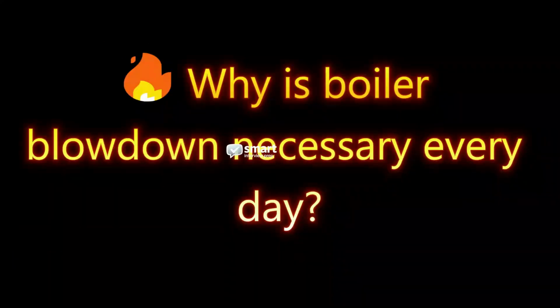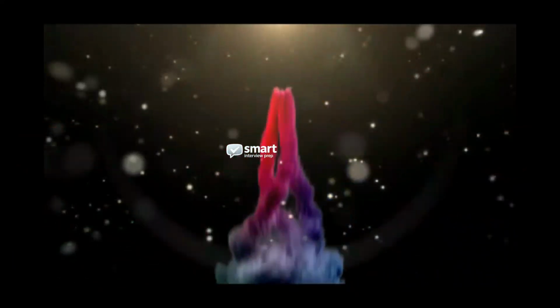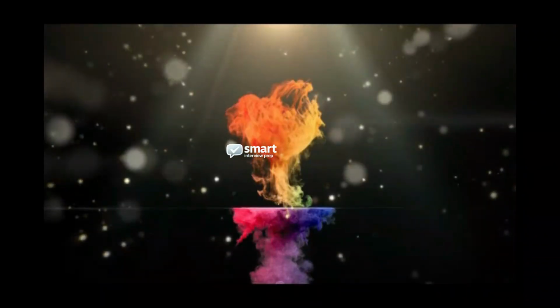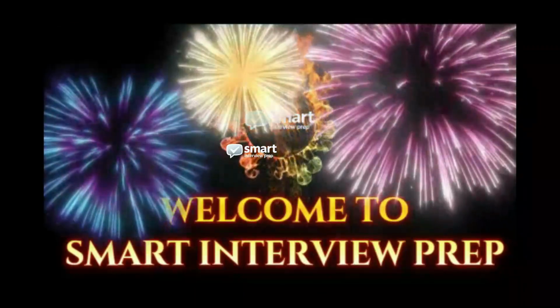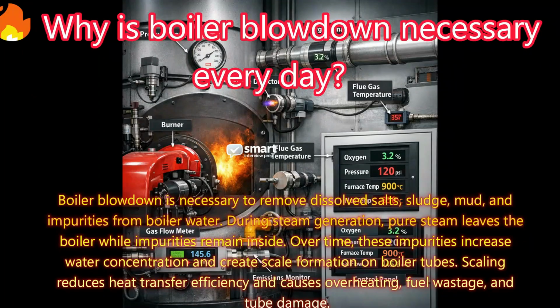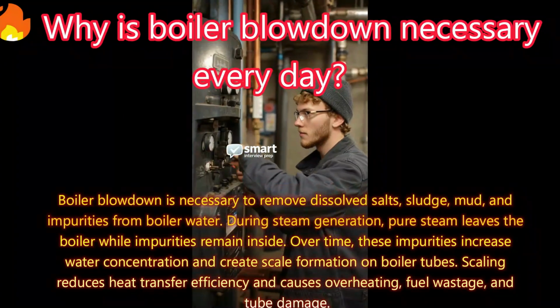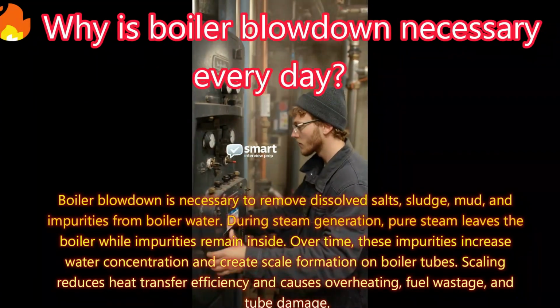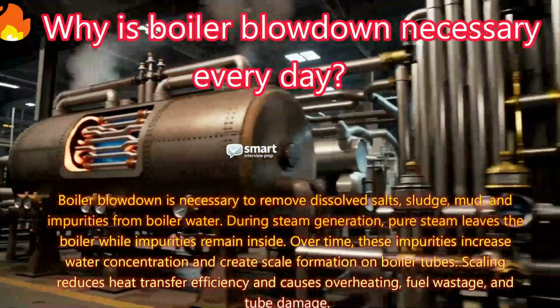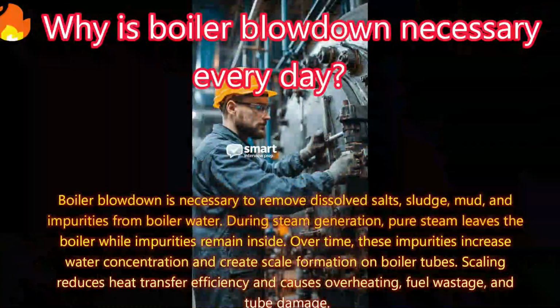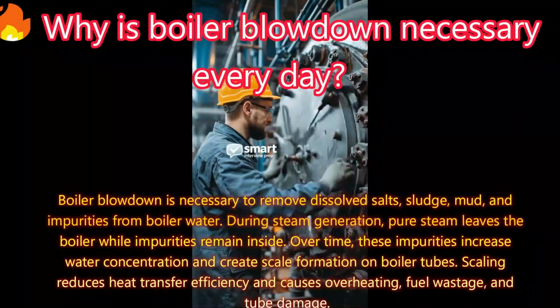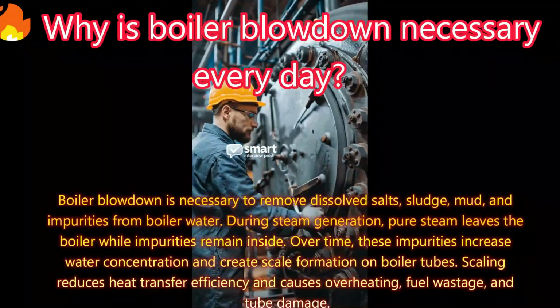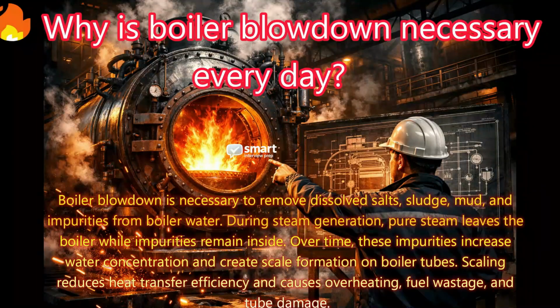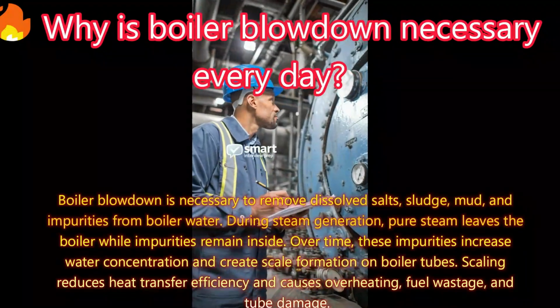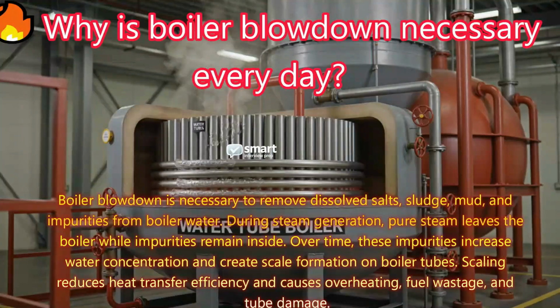Why is boiler blowdown necessary every day? Answer. Boiler blowdown is necessary to remove dissolved salts, sludge, mud, and impurities from boiler water. During steam generation, pure steam leaves the boiler while impurities remain inside. Over time, these impurities increase water concentration and create scale formation on boiler tubes. Scaling reduces heat transfer efficiency and causes overheating, fuel wastage, and tube damage.